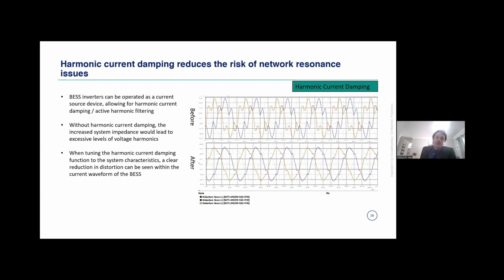So what we applied on the BESS inverters themselves was to tune our harmonic current damping functionality to ensure that we address the critical harmonics that were present on the system before we connected our battery system. If you look at the graphic to the right, I think it's very apparent that before, we were sitting with a very high fifth harmonic current in the system, and after we applied the harmonic current damping, we were able to reduce that to within acceptable levels, even when operating with fewer generators online. And yeah, that is my story.